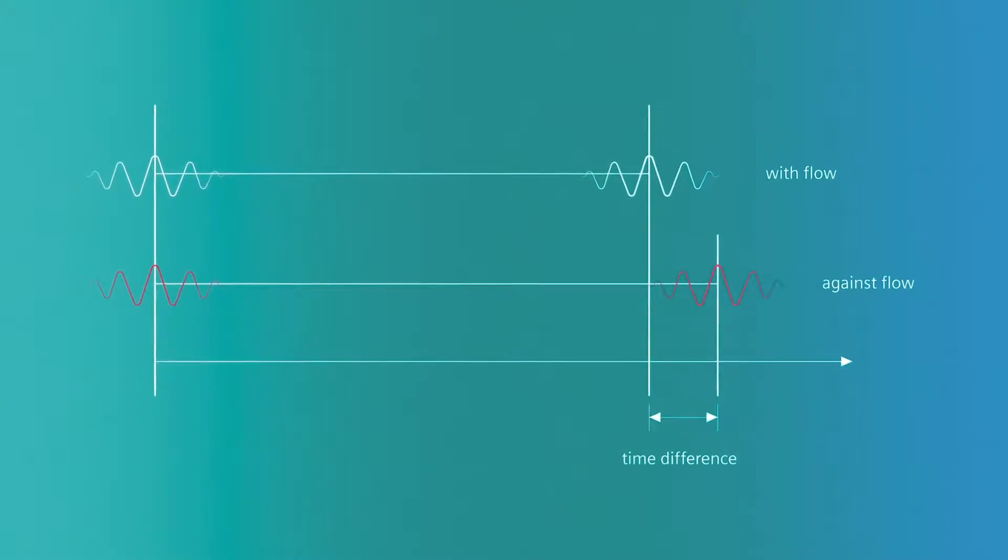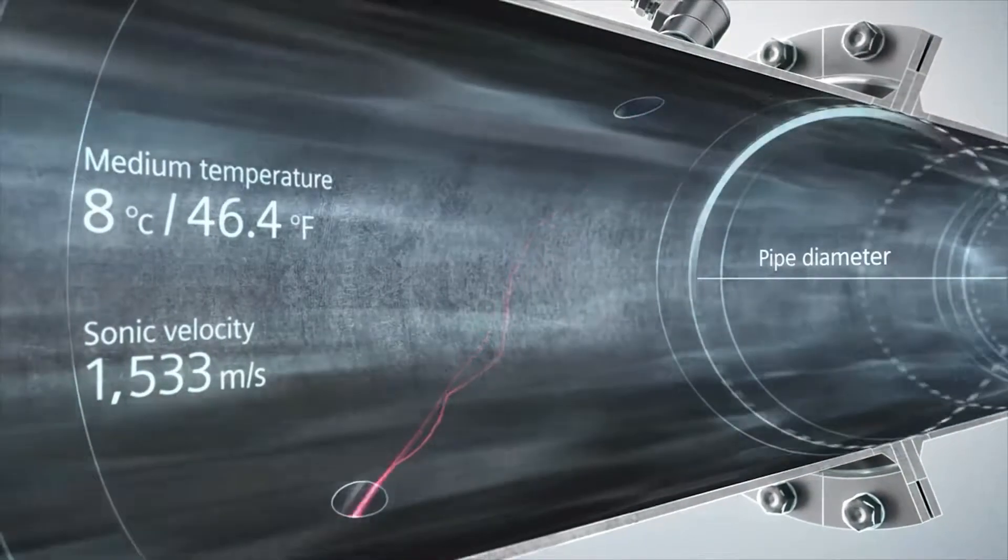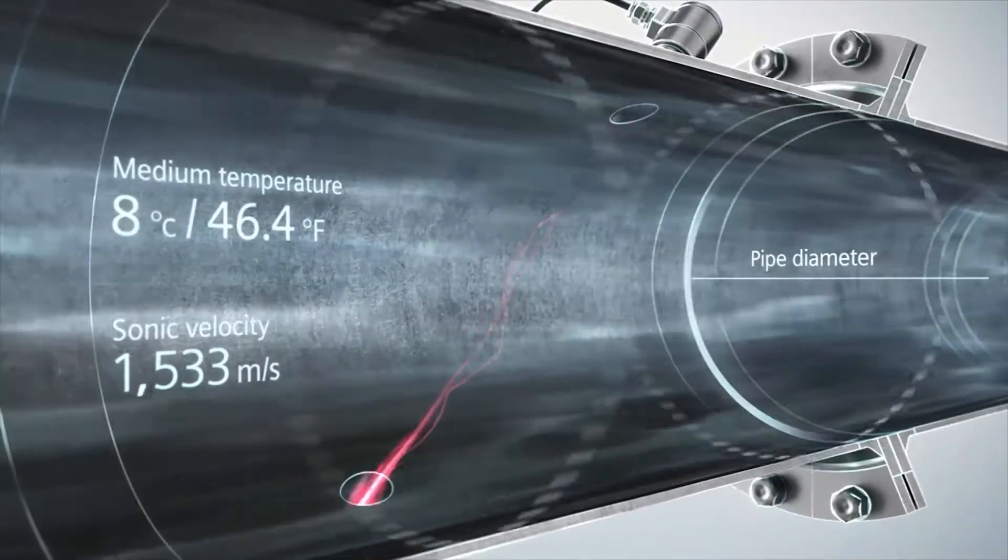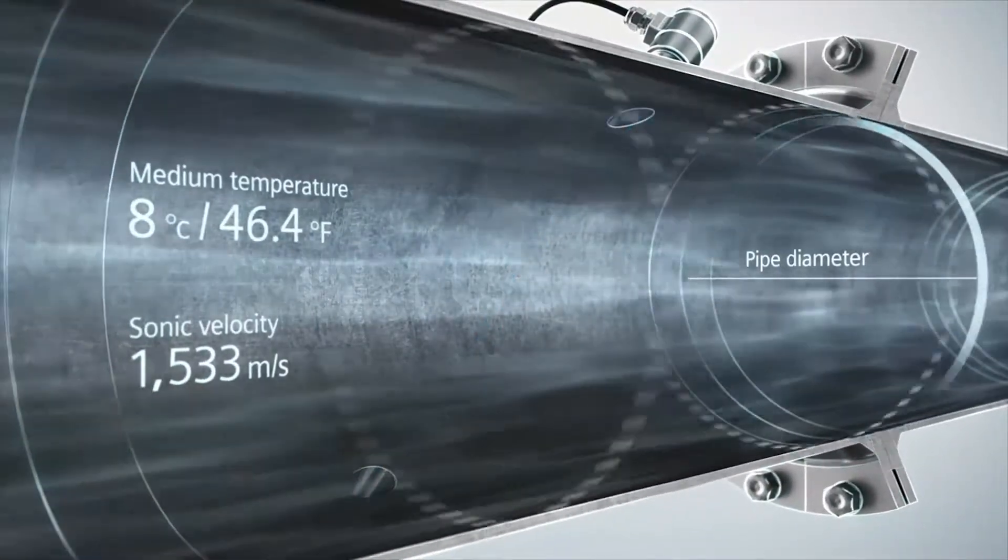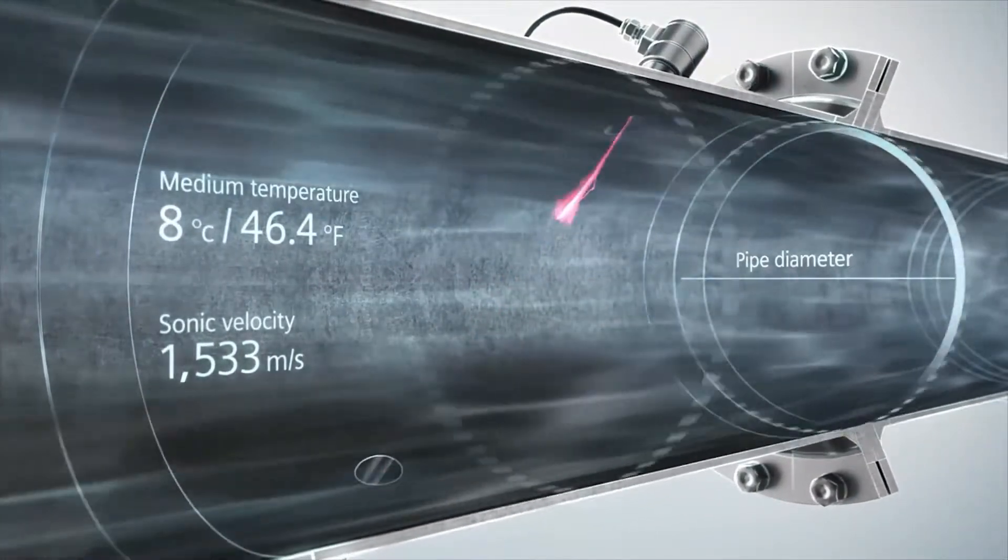Combined with the known area inside the pipe and the measured sonic velocity and temperature of the media, it is possible to accurately measure the volume and also to derive parameters like density and viscosity.